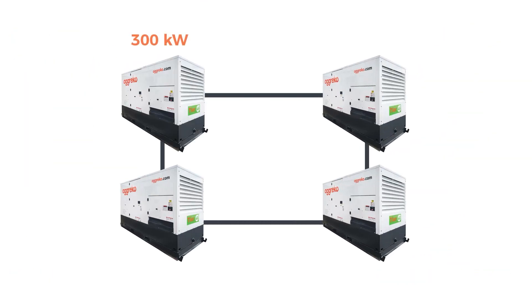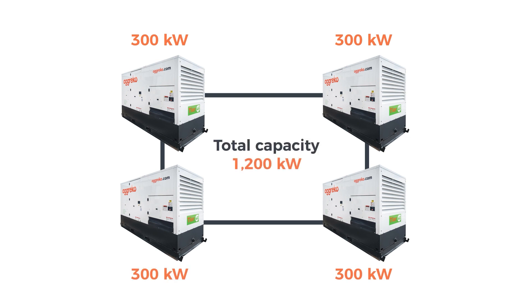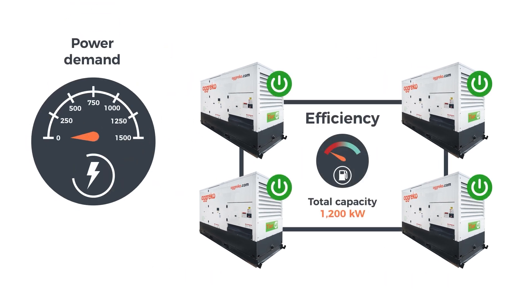Using Aggreko's Load On Demand solution, you can have four 300 kW generators, providing a total of 1,200 kW — plenty for peak demand. Current demand is a steady 200 kW, so three of the generators automatically shut down. When more power is required, the next generator automatically starts to meet demand.